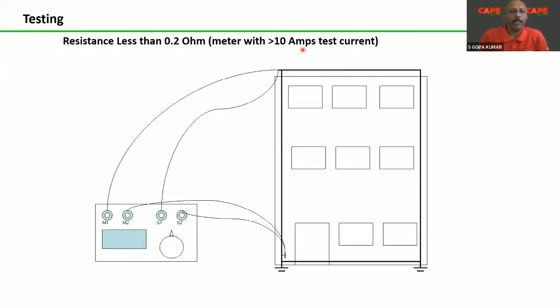Actually, it won't work. Even the meters used for testing earth pit resistance, the Wenner method, 4-pole method, 3-pole method, those meters are used for this testing, but please understand that it won't work. The minimum requirement is that the meter used for this testing shall have a test current of minimum 10 amps.